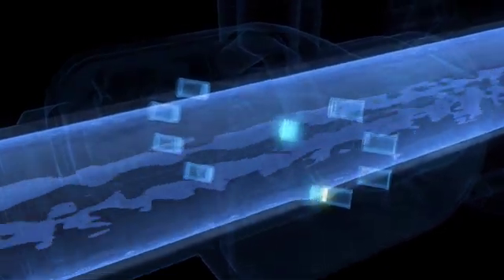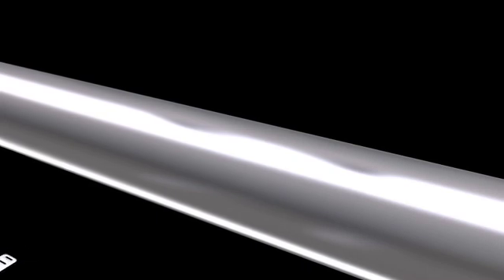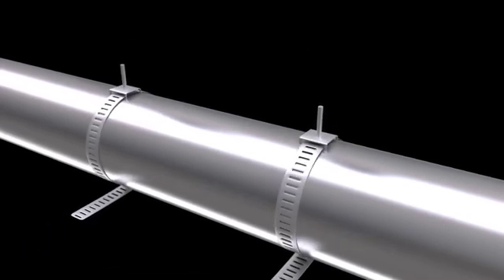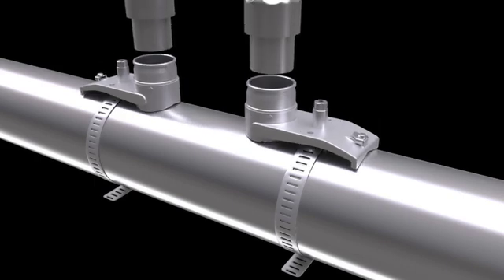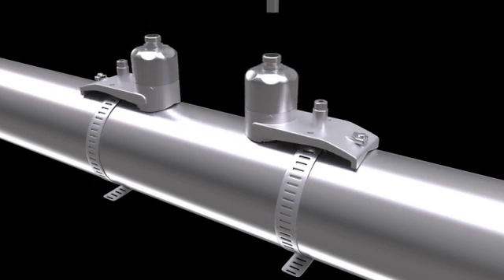For ultrasonic flow measurement, the sensors do not necessarily have to be fitted into the pipe wall. With a clamp-on system for example, the sensors are fastened directly onto the outside of the pipe. They can be retrofitted at any time without interrupting the process.